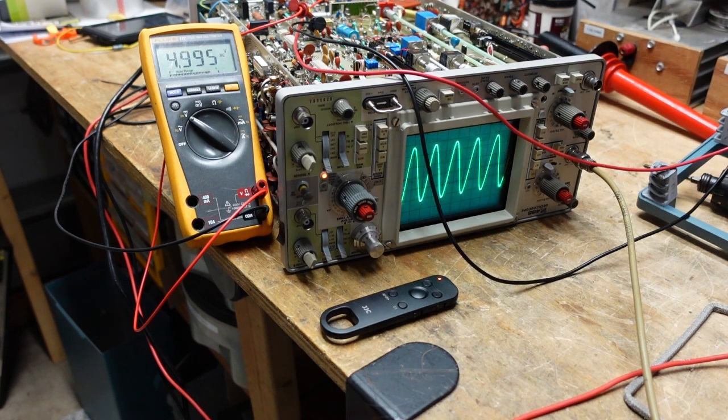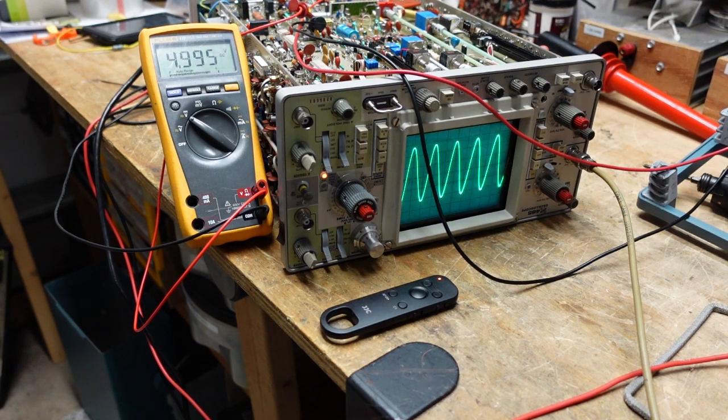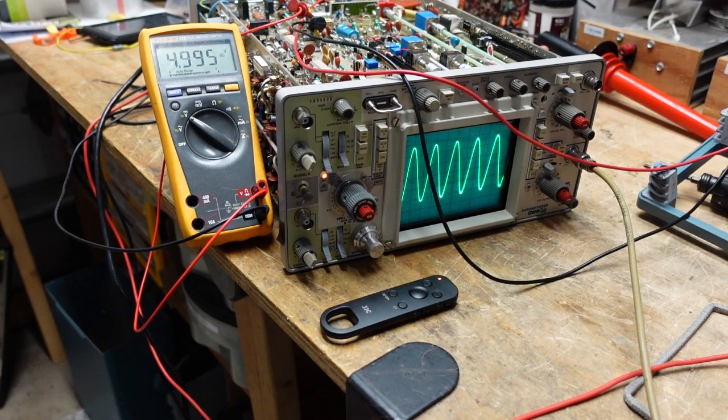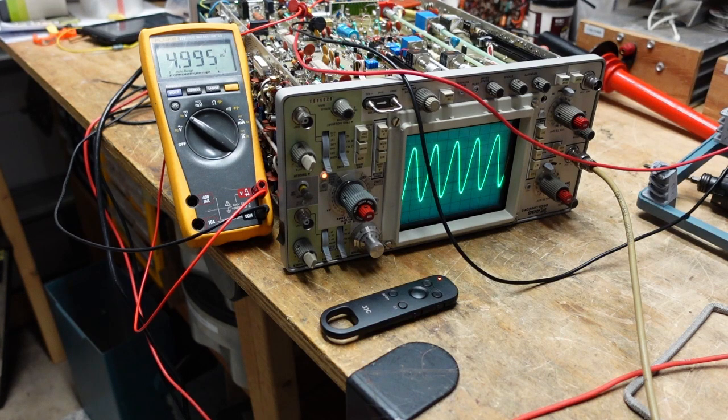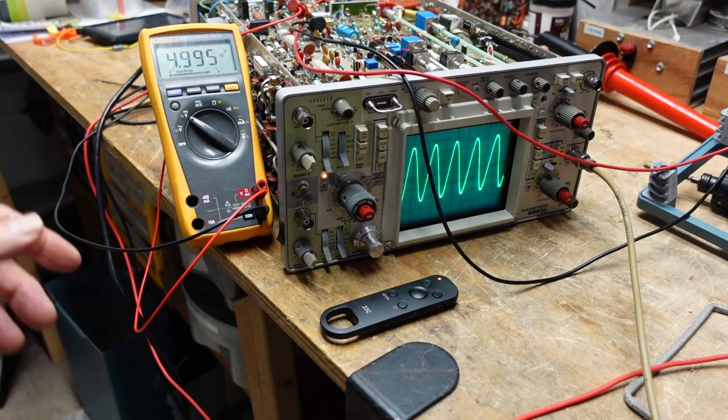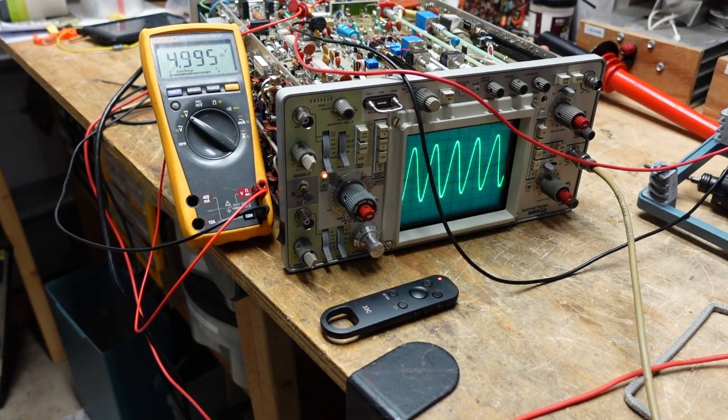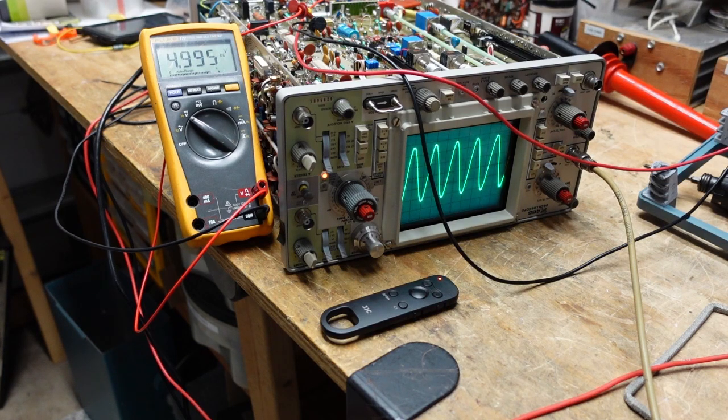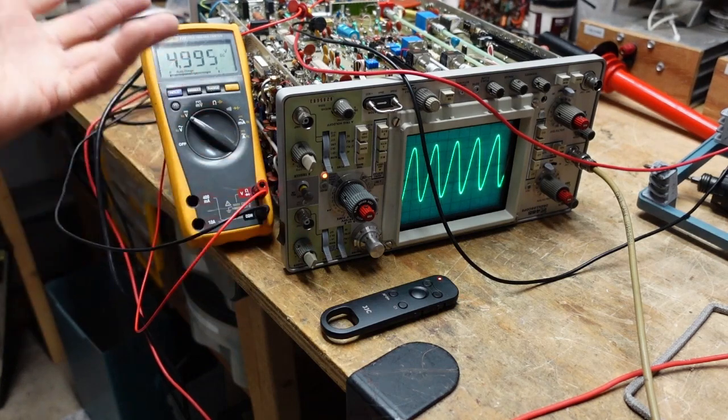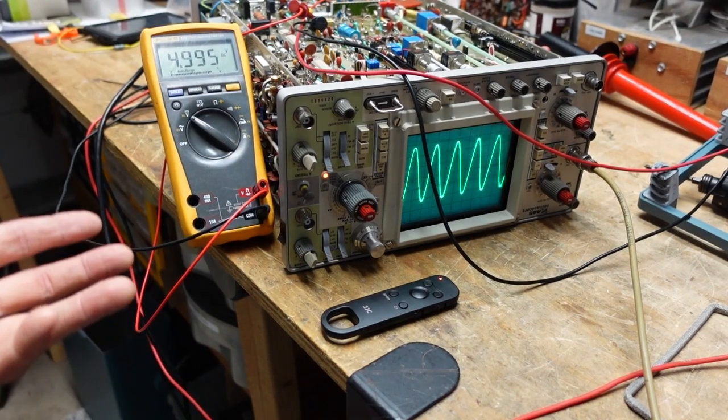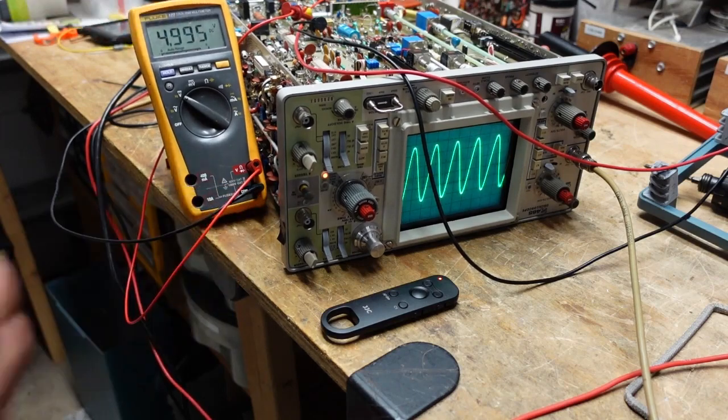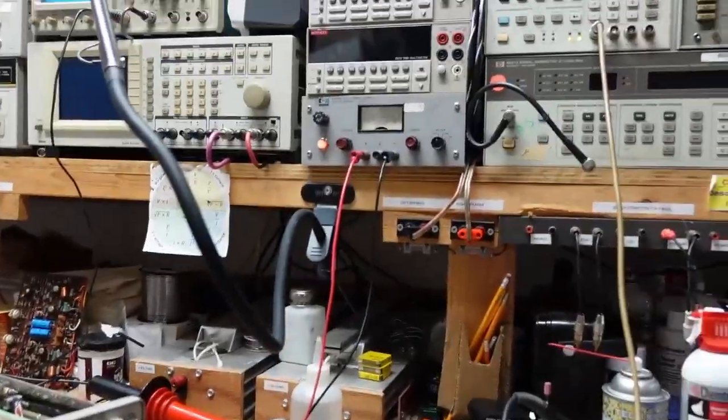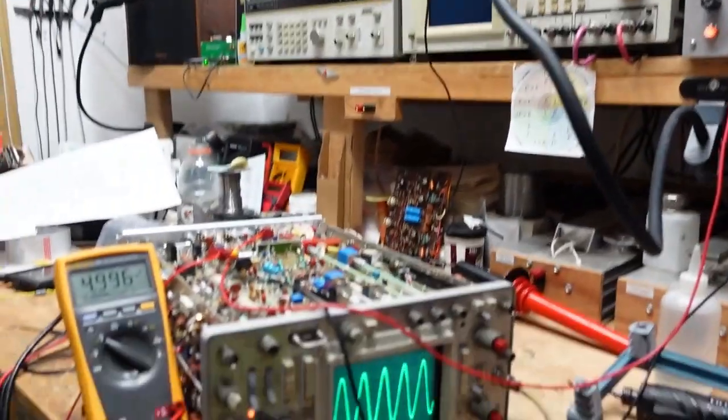And I need to put a video up here because this was not what I thought it was. Every other high voltage multiplier I've ever seen shorted out—I've never seen one do what this is doing. So I suspect there may have been a problem with my measurements. I'm probably going to go back and check that out again, but I needed to put this up here to show you that we all make mistakes. And before ordering an expensive part or writing something off, which I was ready to do with this, it pays to look at all the little things. Power supplies are an excellent place to start. Once I saw what was going on here, I could have fixed the supply, but it would have been a waste of time to fix a power supply on something that still has other issues. So I decided to just inject from my bench power supply, and that's this little guy right up here—that's where I'm feeding in.